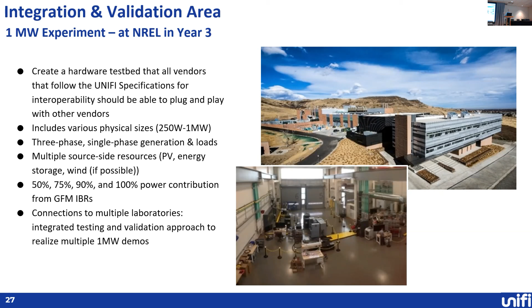Right now, today, if I was a single vendor on a single power system, I can build a grid forming inverter system that will work. But one of the things we really need to validate is, can we just have any vendor follow a set of rules and then all the inverters work together, share power, and do that properly? That's what we're going to be setting up in this facility, this kind of test bed where we'll be bringing in multiple vendors that are all following the rules, but we don't know the actual innards of all their control algorithms, and making sure they can provide stable grid operation at a variety of different contributions from inverter-based resources.